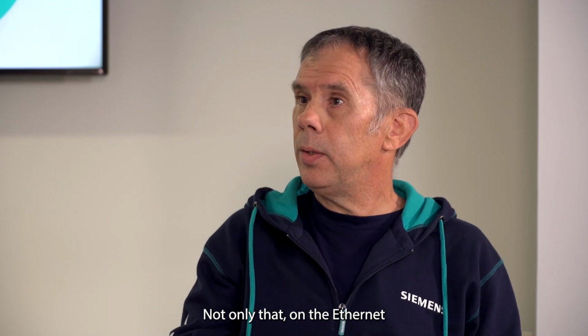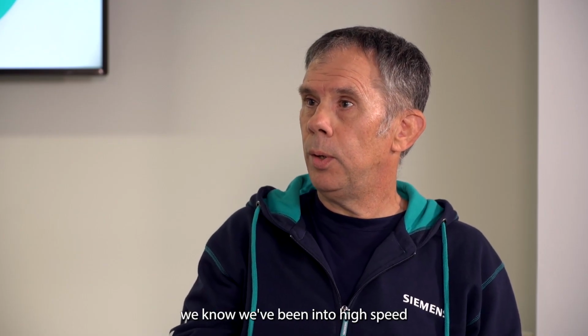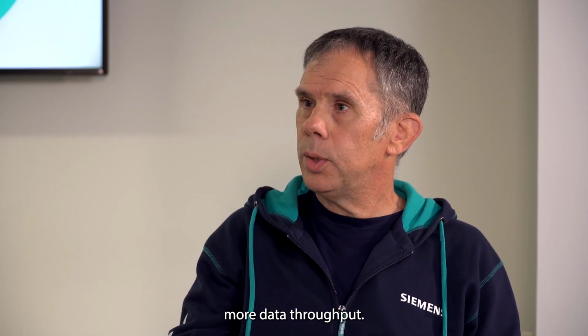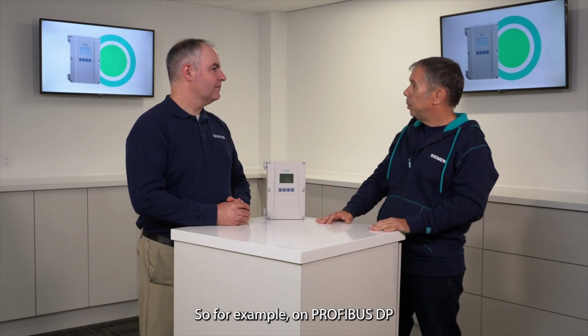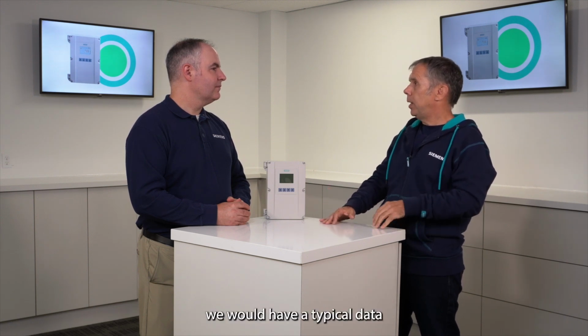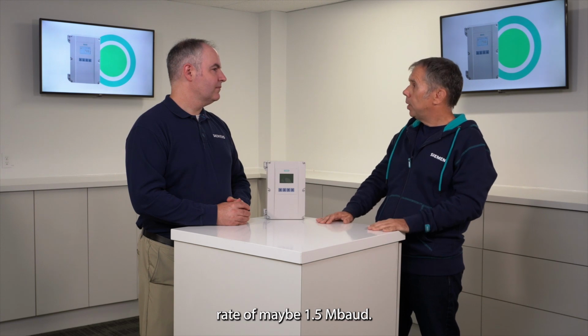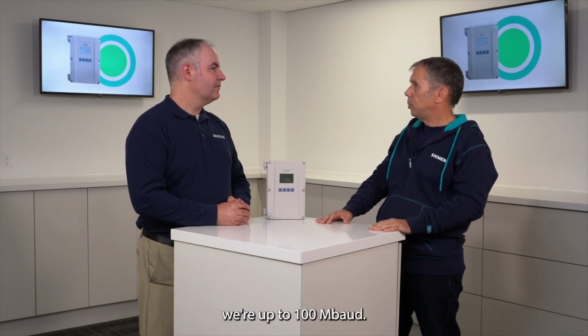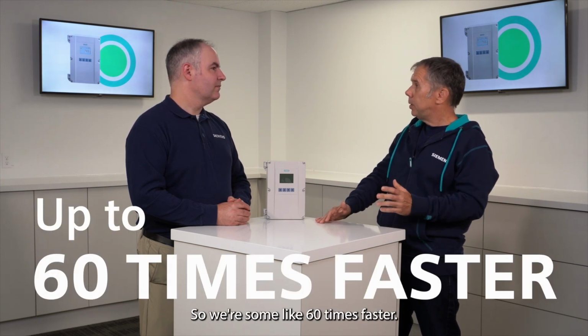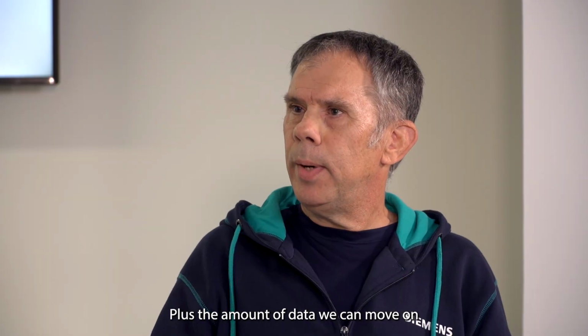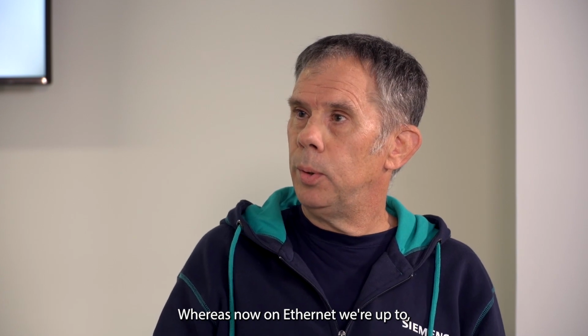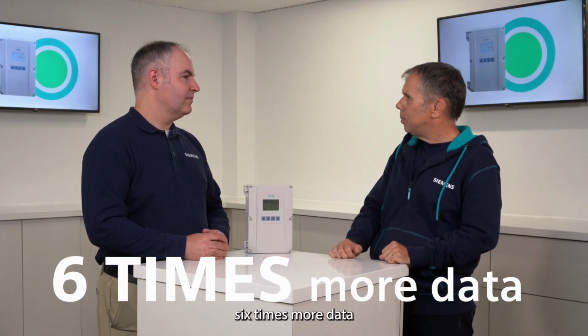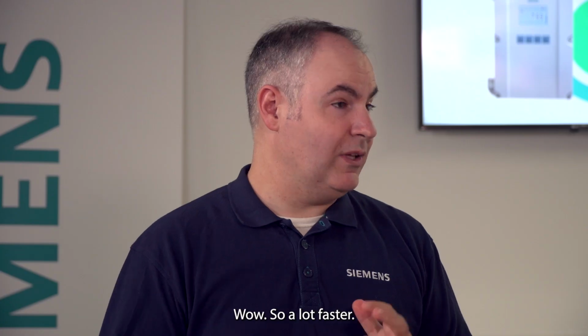Not only that, on the Ethernet-based protocols, we now move into higher speed, more data throughput. So, for example, on Profibus DP, we would have a typical data rate of maybe 1.5 megabaud, whereas now on Ethernet we're up to 100 megabaud. So we're something like 60 times faster. Plus the amount of data we can move on Profibus DP, it's 244 bytes. Whereas now on Ethernet, we're up to 1472 bytes. So again, 6 times more data we can actually move as well. Wow, so a lot faster.